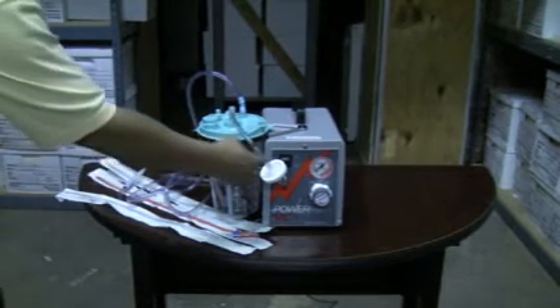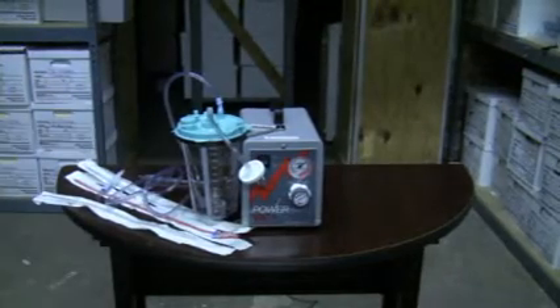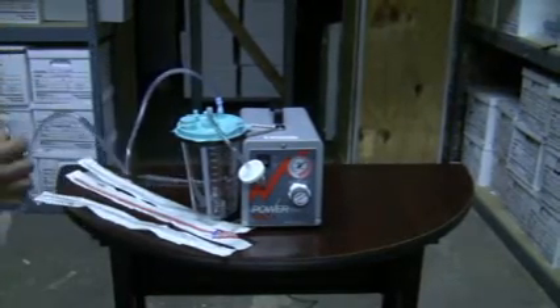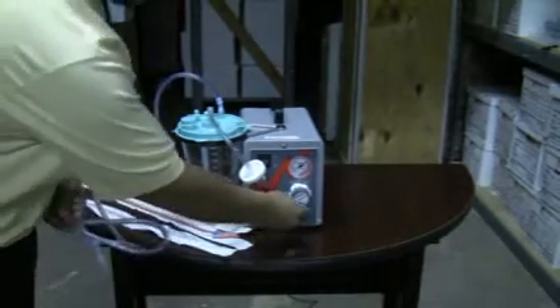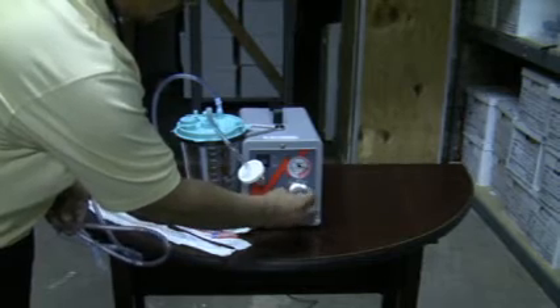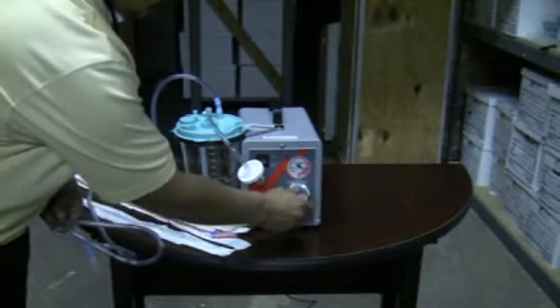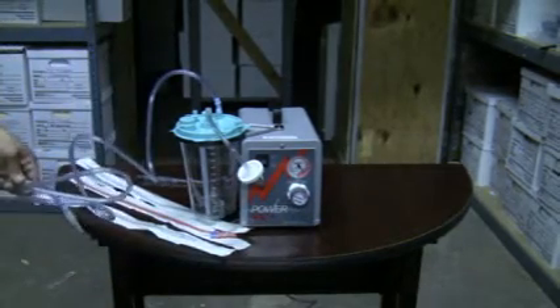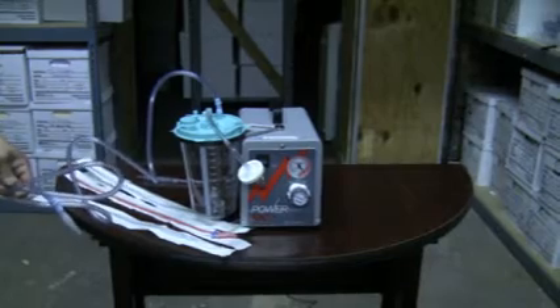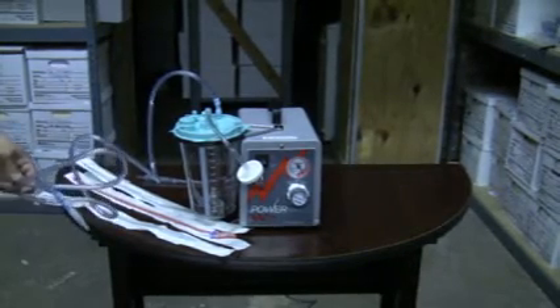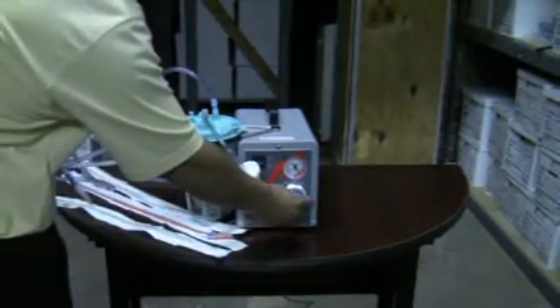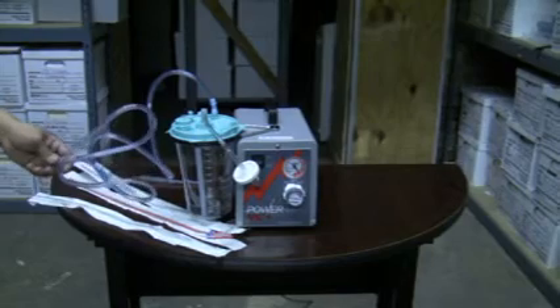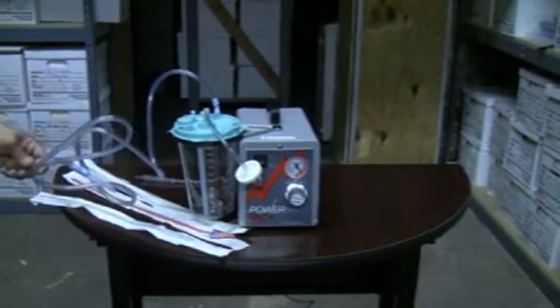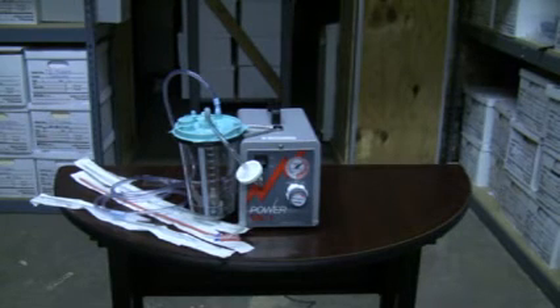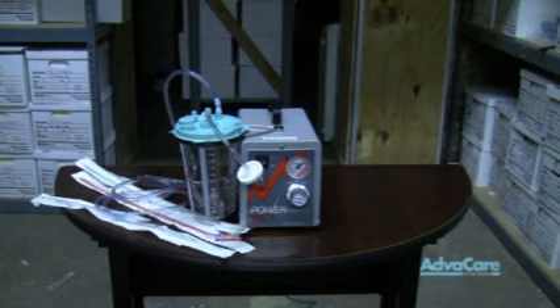If at any time when you do power on and you do have your vacuum machine power with vacuum present, but you're unable to adjust any vacuum pressure with your knob selector, the actual pressure gauge selector knob may be defective and your intermittent suction machine may need to be switched out. So if you're unable to adjust any vacuum pressure, please contact AdvaCare Systems to have your intermittent suction machine replaced. Once again, this is your intermittent suction machine for continuous or intermittent suction procedures for your patient.